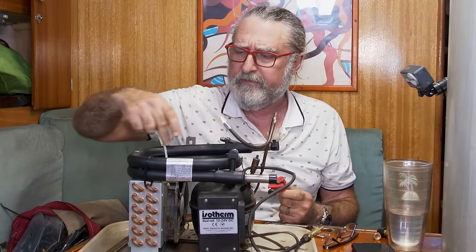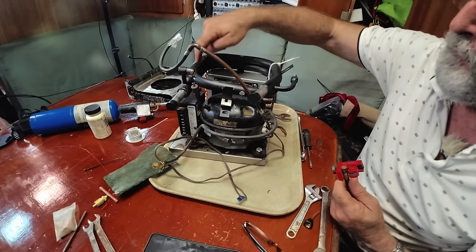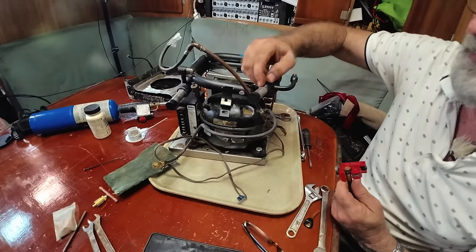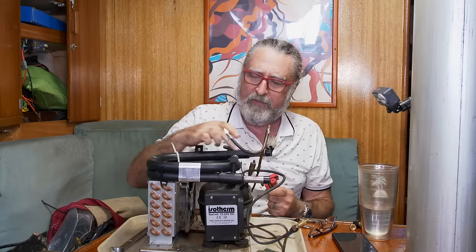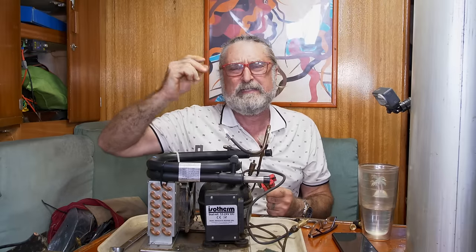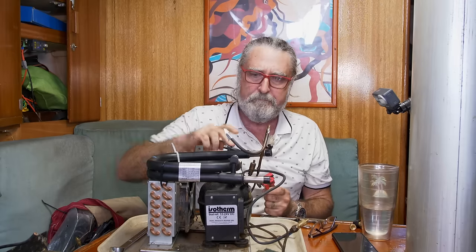If you hook one of these up, you're gonna be asking yourself what is the inside and what is the, oh, let's first talk about the water condenser here. The water goes through an inner tube, and then there's this outer tube that's welded on. It's all made out of titanium, which is kind of cool. And according to the manufacturer, the inner tube has been twisted in a way so that there's fins that cause turbulence both in the water and in the gas passage.